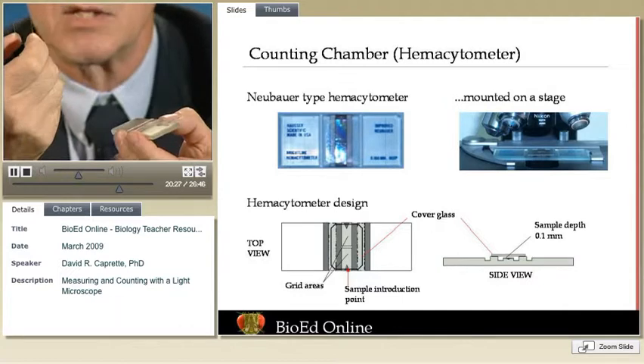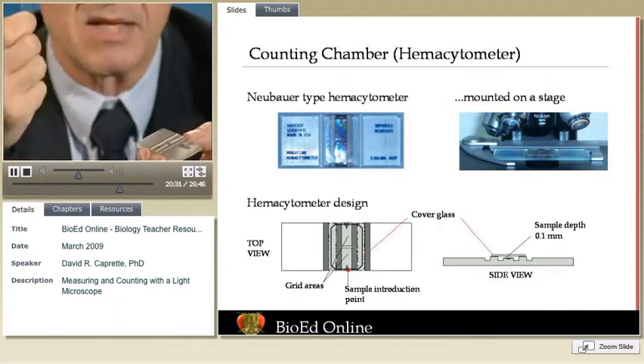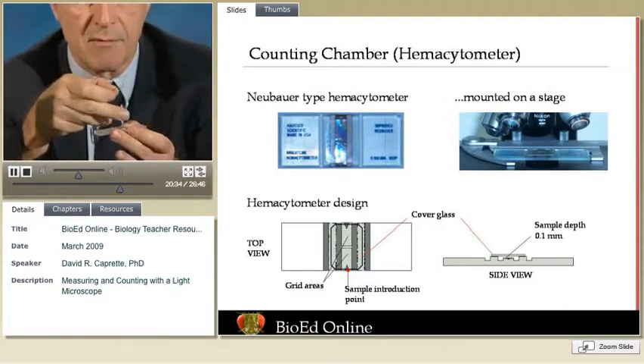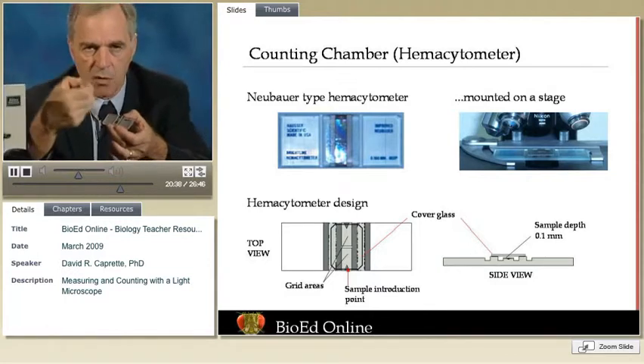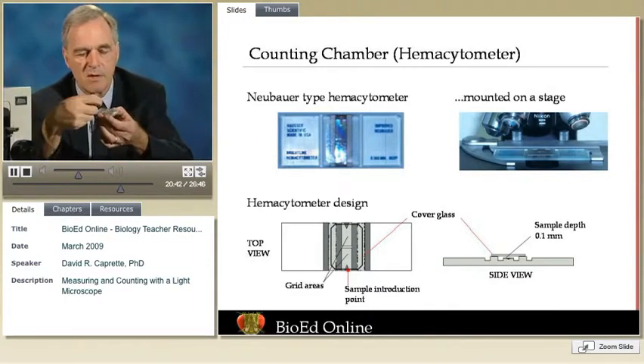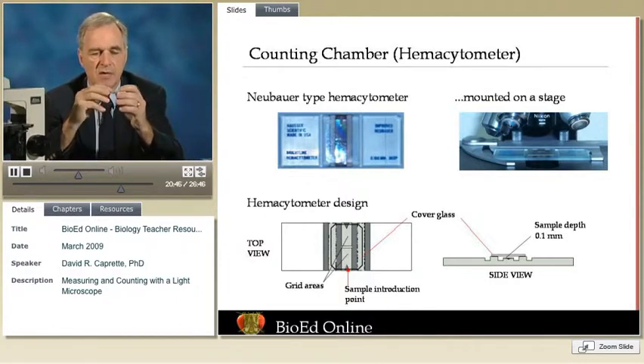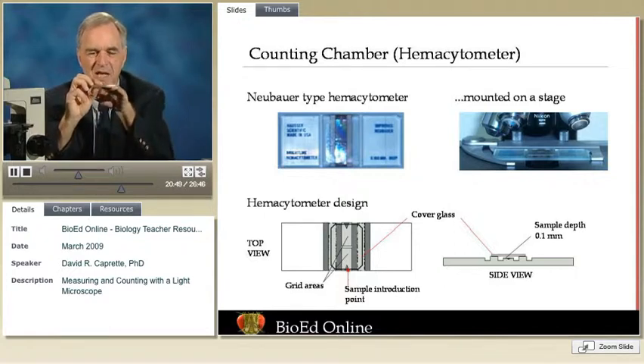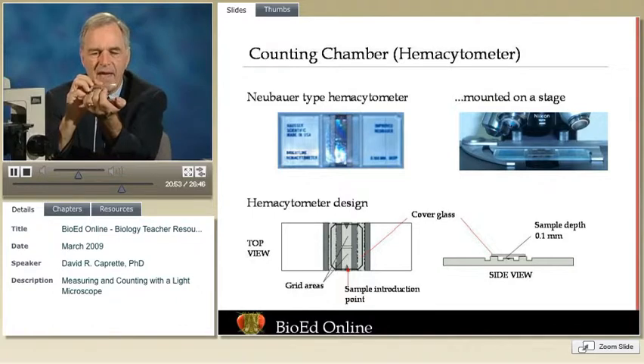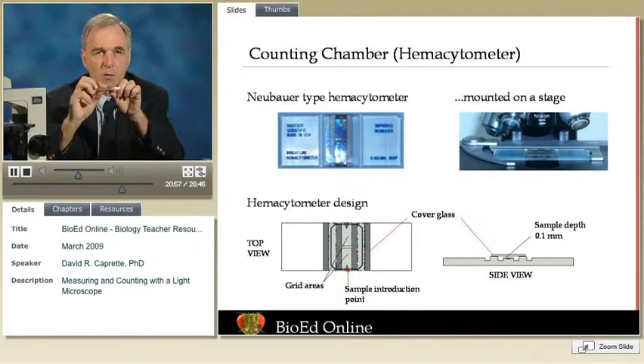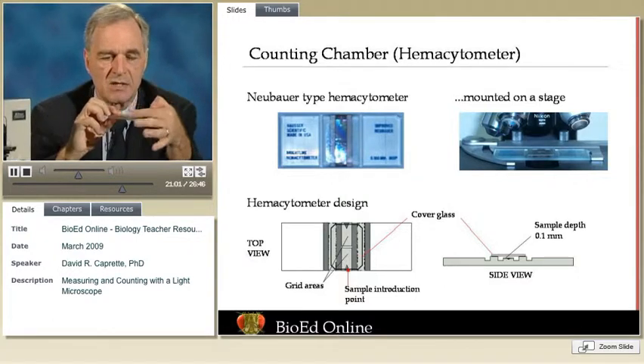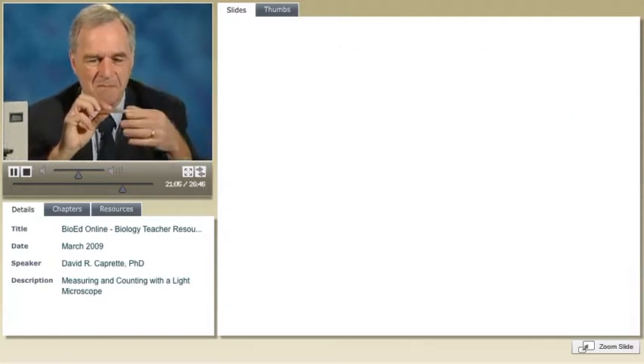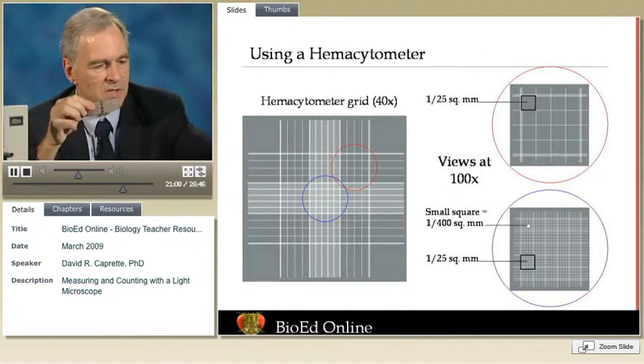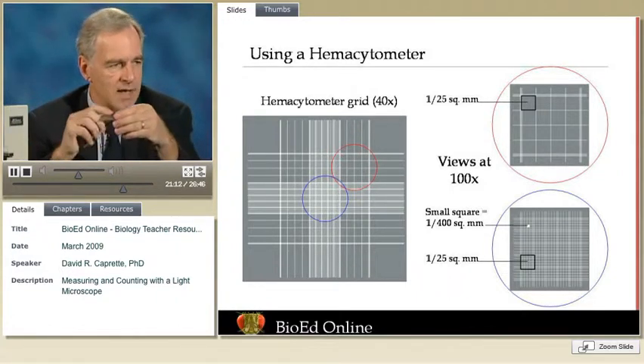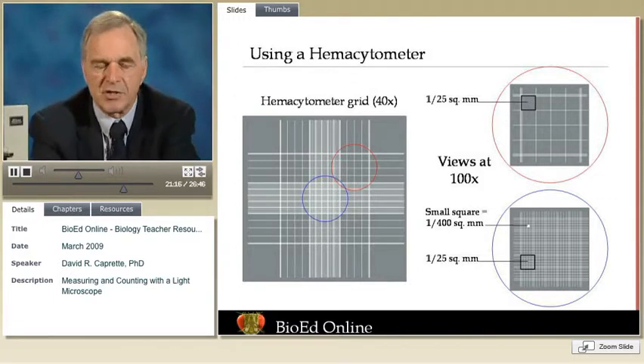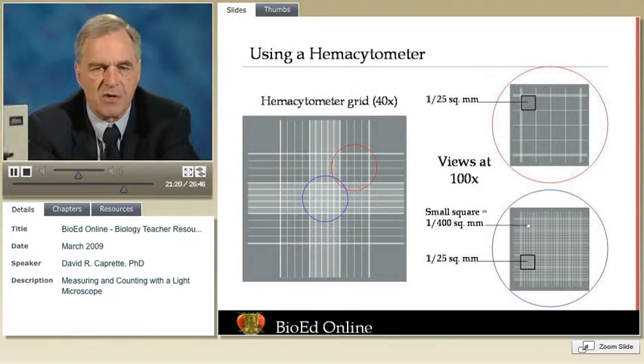The cover slip is typically 0.4 millimeters thick. That makes it heavy enough so it can compress any liquid that's on top of the mirrored surface, and it isn't pushed up or floated by the specimen that's underneath. The cover slip rests on a couple of posts so that there's a gap between the mirrored surface of the hemacytometer itself and the bottom of the cover slip. And that gap is quite accurate. It's generally 1/10 of a millimeter deep. So there's space underneath the cover slip there, and it's a calibrated depth. Now, on the mirrored surface of a hemacytometer is a grid. And the grid literally looks like this, very finely etched. The center part of the grid, you might note, superficially resembles a tic-tac-toe board.